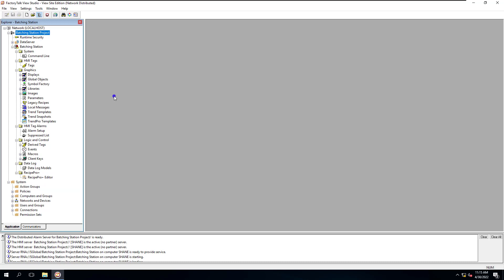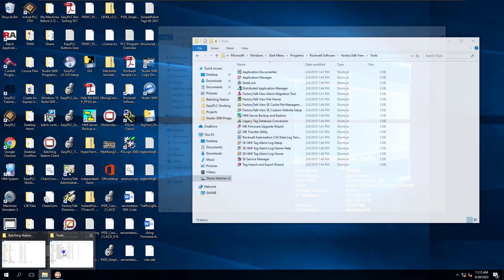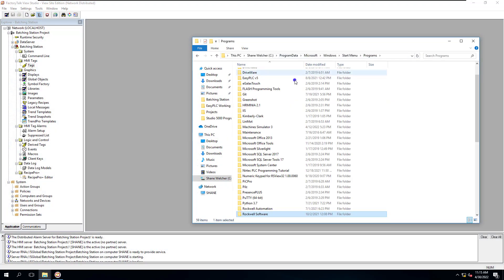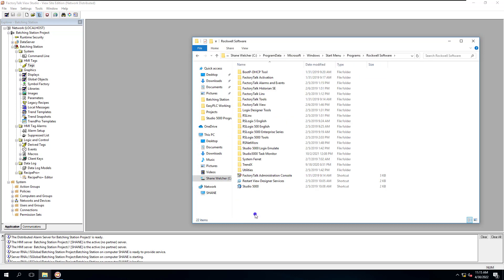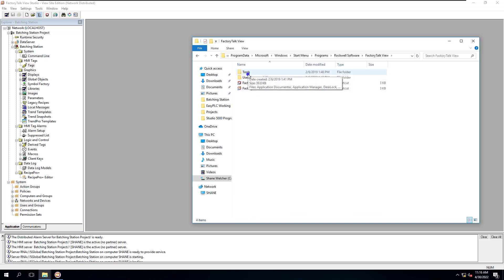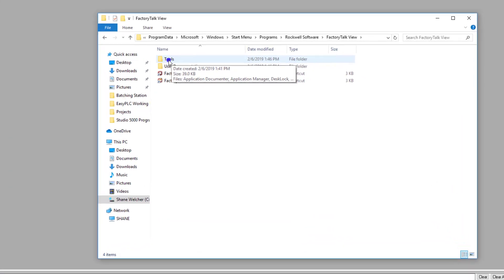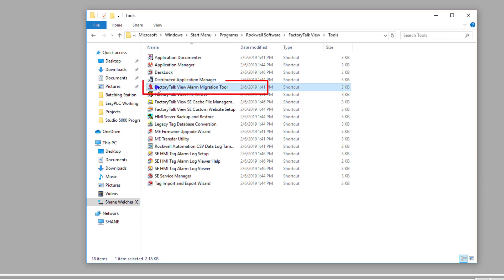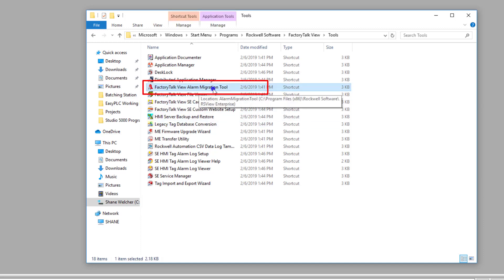We're going to add that here in a second. First, we need to convert this tag. So let's go to our folder — navigate to Rockwell Software, then to Factory Talk View. I'm showing you this in Factory Talk 10. You can do this in Factory Talk 12 if you've already migrated up and save your application, but you should have done this beforehand. If you're seeing that warning window, go ahead and be proactive and do it now. So in Tools, go to Factory Talk View Alarm Migration Tool.